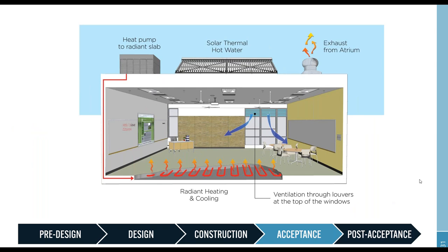There we go. Better. So the way that this specific project was designed was almost like a living, breathing building. We used natural ventilation coming from above the windows through natural ventilation terminals, and that pull and had exhaust fans in this main school's atrium, allowing the exhaust fan to suck air through the atrium, through the classrooms from the outside to provide natural air and fresh air into the building.